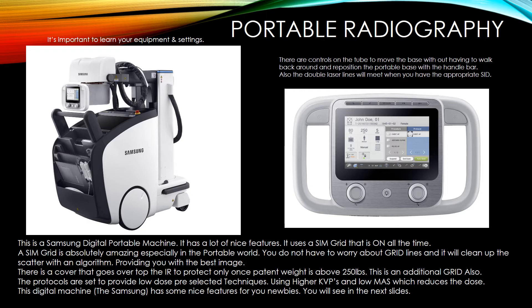It is important to learn your equipment and your settings. This is a Samsung digital portable machine with many nice features. It uses a SIM grid that is on all the time — a SIM grid is absolutely amazing, especially in the portable world. You do not have to worry about grid lines; it will clean up scatter within an algorithm, providing the best image. You don't have to worry if you are slightly off angle. There is a cover that goes over the IR to protect when the patient weight is above 250 pounds, which is also an additional grid to help clean up scatter. Protocols are set as low-dose pre-selected techniques using higher kVps and low mAs to reduce dose.